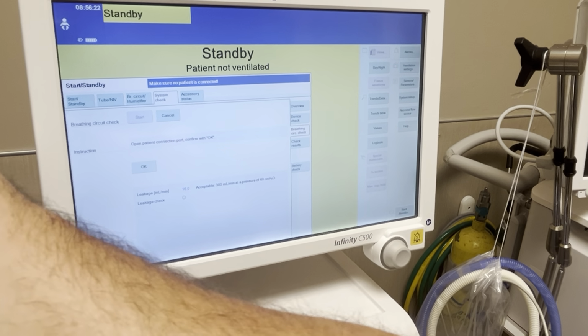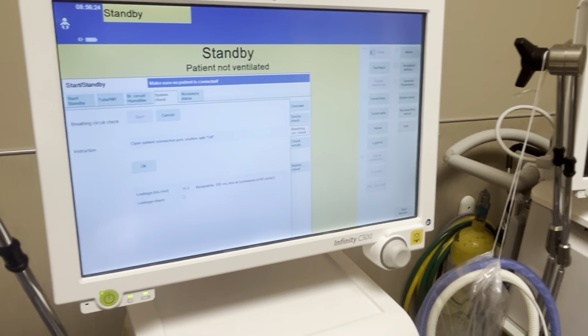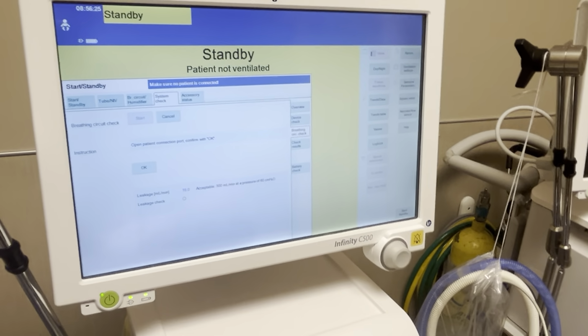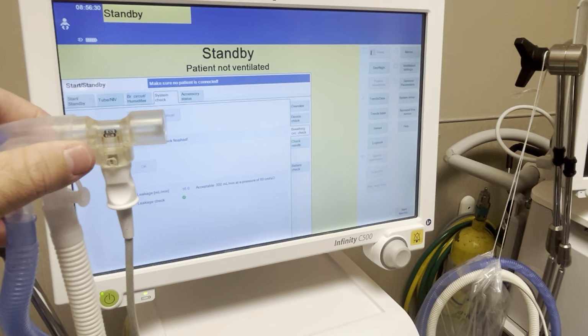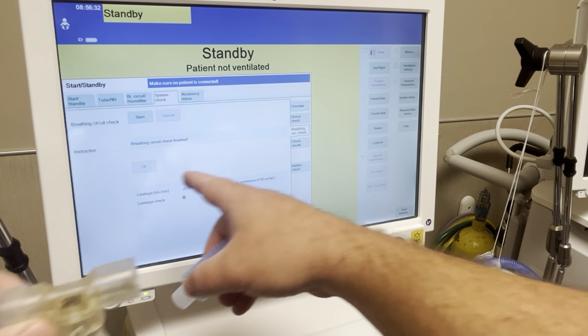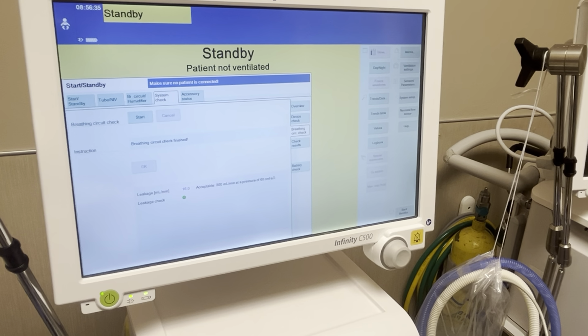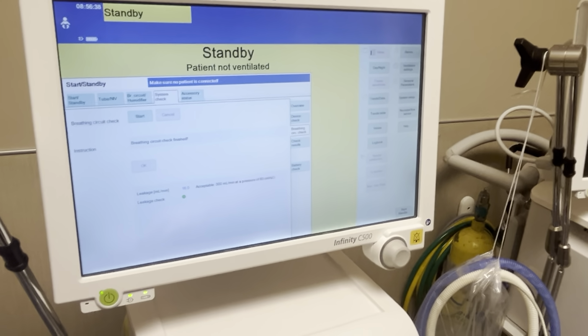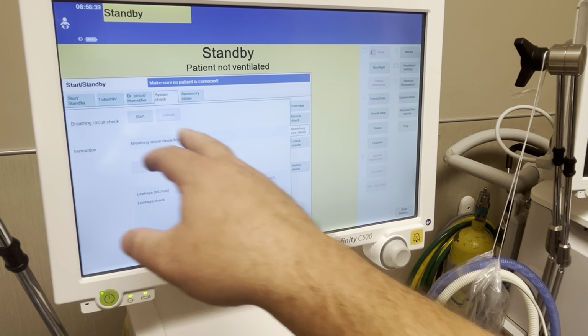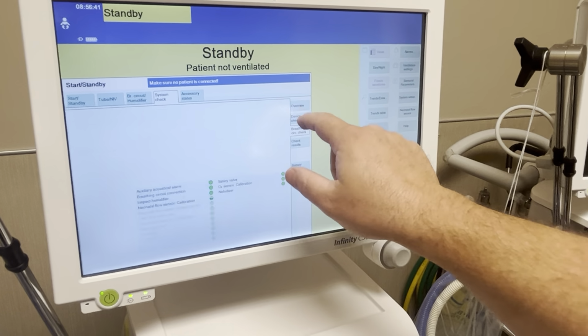So now it wants me to open the connection port, so I'll just take the lung off. See, take the lung off, push OK, and it checks the resistance, and now it says check finished. So we passed our breathing circuit check, so I know my circuit is installed correctly. I'll go here to device check. You can see last time it was done, everything passed. That's what all these green dots are.